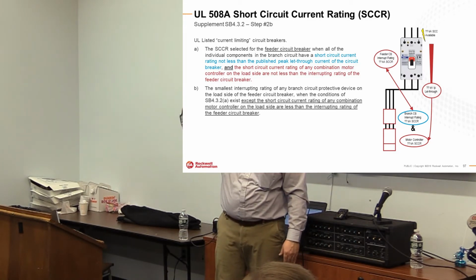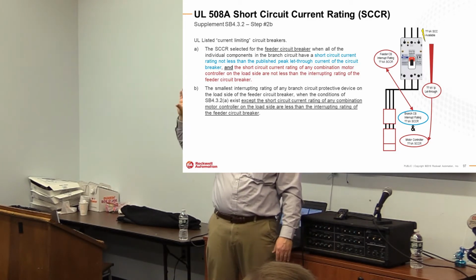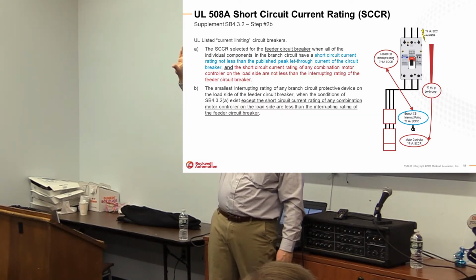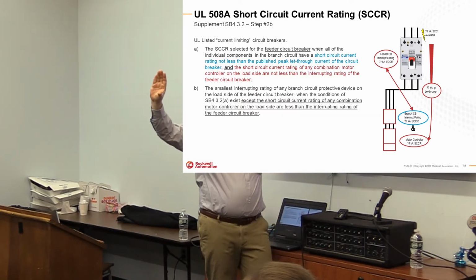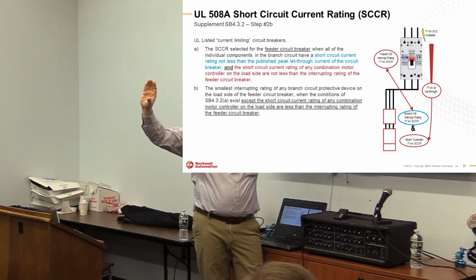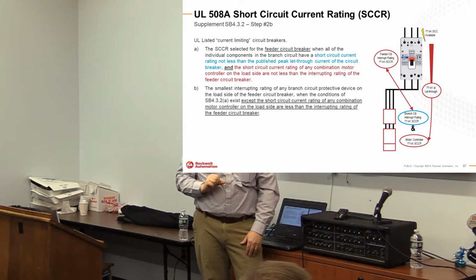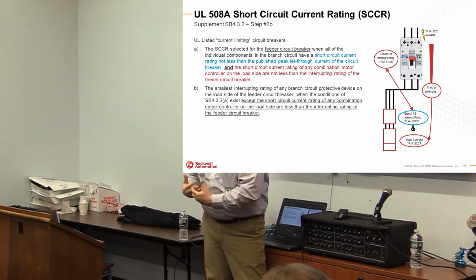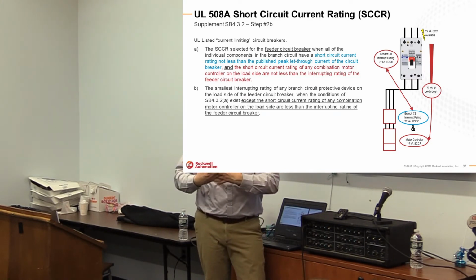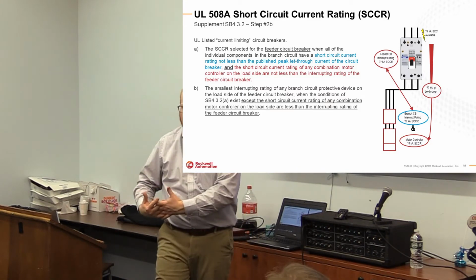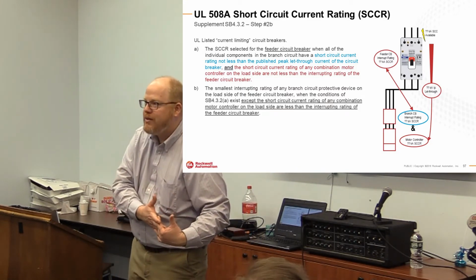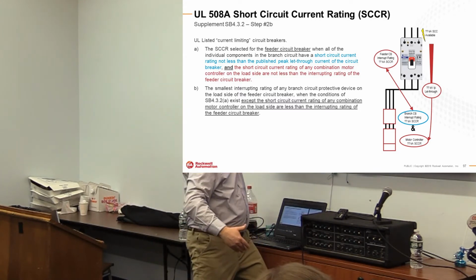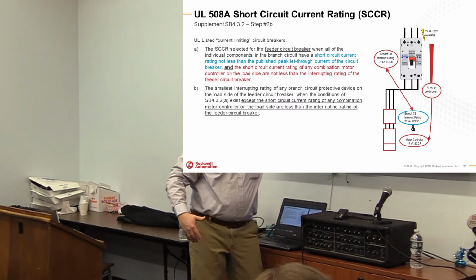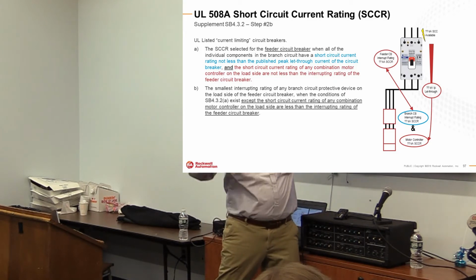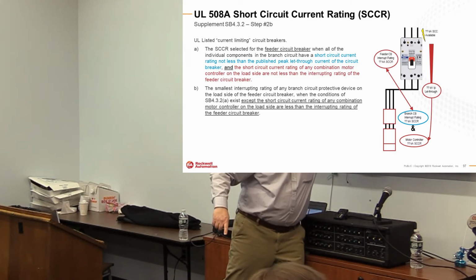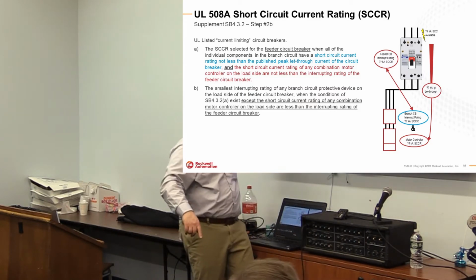What cannot happen, and people who misinterpret this go, oh, I got one of them current limiting breakers that I paid a lot of money for. I could put a whole bunch of crappy branch protection down below it, and I'm protected. That is not correct. I have found this is actually a very lofty requirement. Quite frankly, these current limiting rules are exceptions, not rules. They should really call them current limiting exceptions to the circuit design. You need to have a well-coordinated set of interrupt ratings at the branch that are as good or better than the feeder, in addition to looking at the peak let-through of the feeder, with all of the components down below.